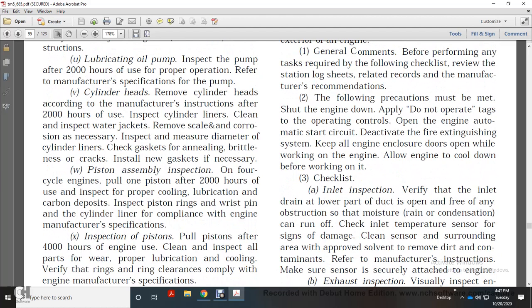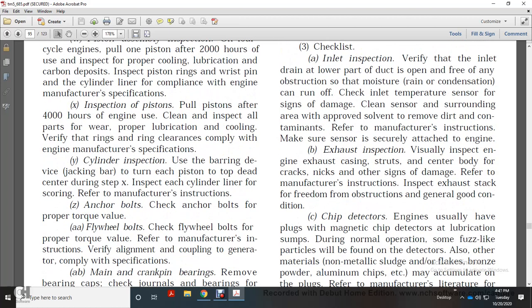Checklist, inlet inspection: verify the inlet drain at the low parts of the duct is open and free of obstruction, so that moisture and condensation can run off. Check the inlet temperature sensor for signs of damage. Clean the sensor and the surrounding area with an approved solvent to remove dirt and contaminants. Following the manufacturer instruction, make sure the sensor is securely attached to the engine.